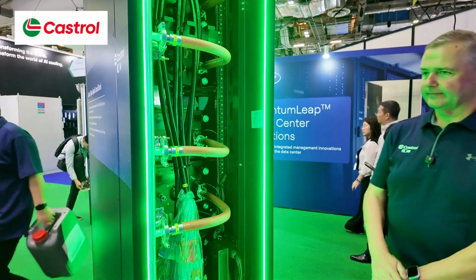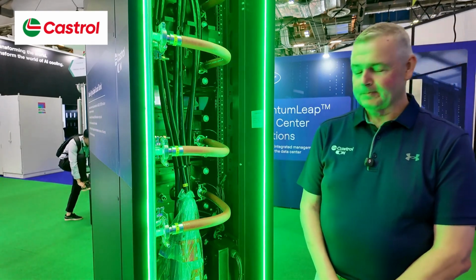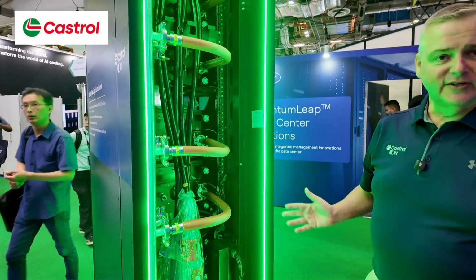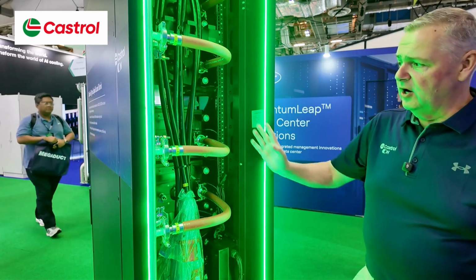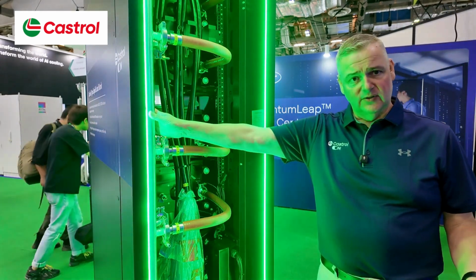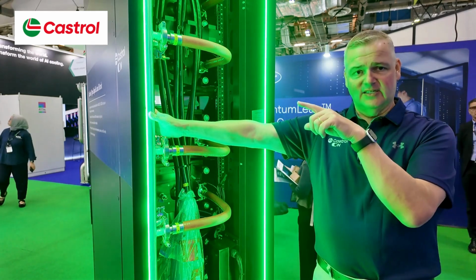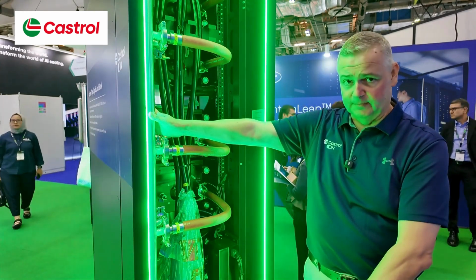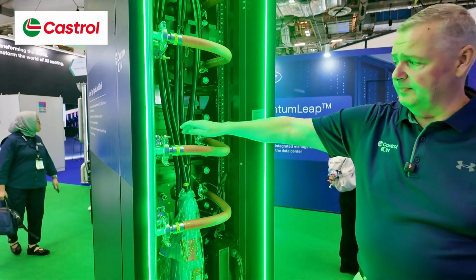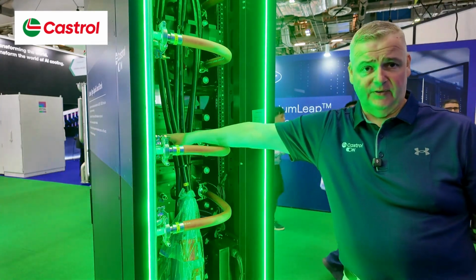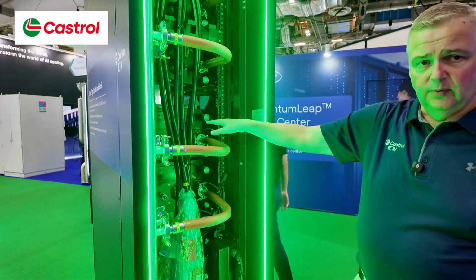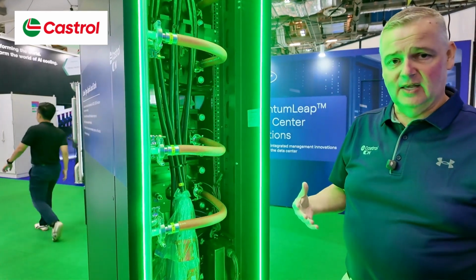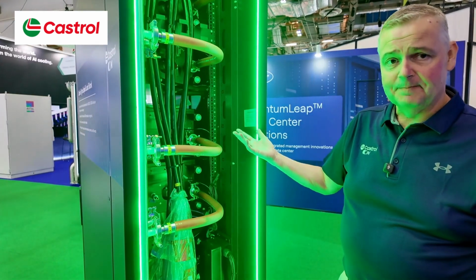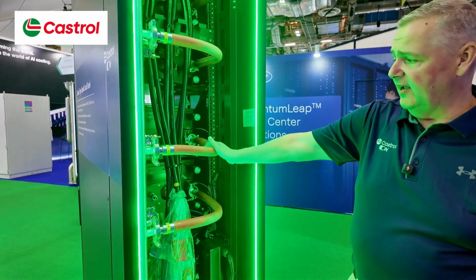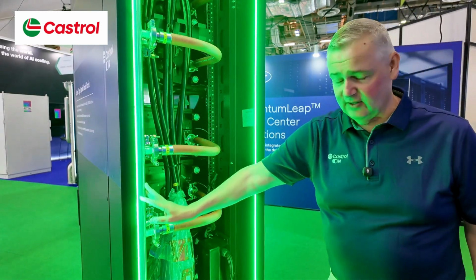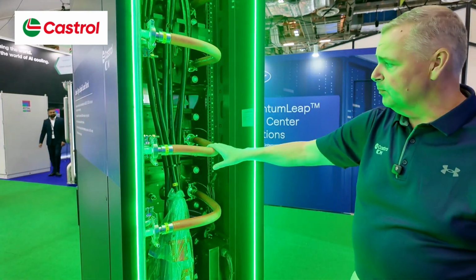Okay, Mark, so what's going on here now? At the rear of the rack, this is more of the water infrastructure. The first thing to point out is the manifolds on the side of the rack. We can feed into the manifold from the top or from the bottom. The blue is the supply of the fluid in. That will go into each of the load banks and then get heated up by the resistors in there. Then it will exit the rack itself through the return manifold.